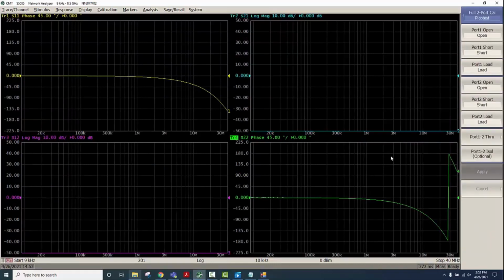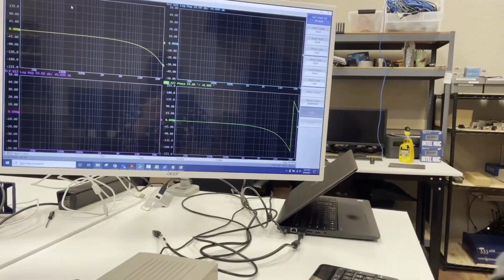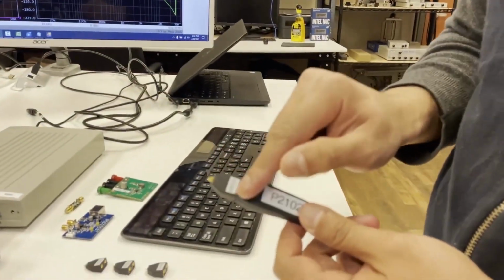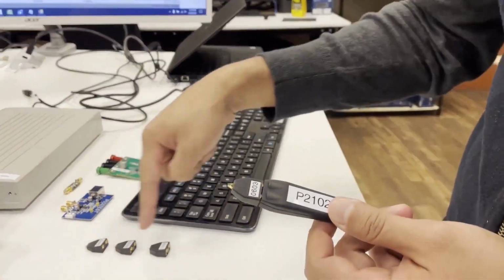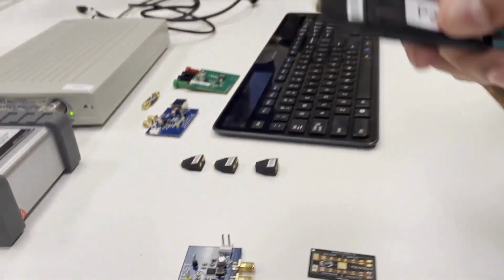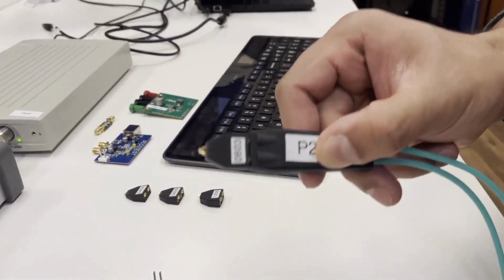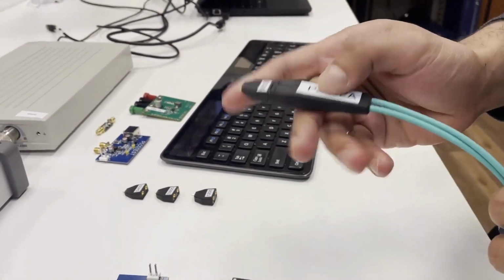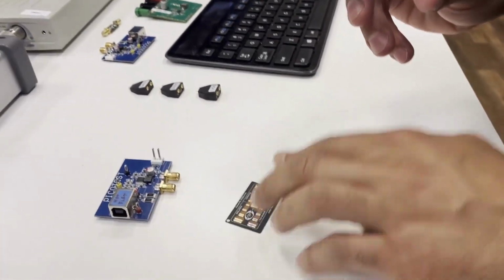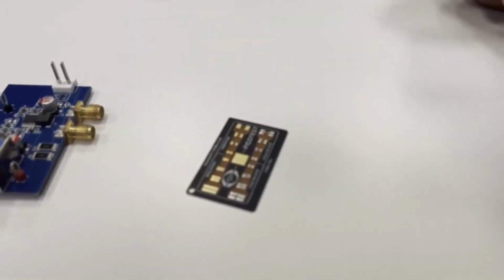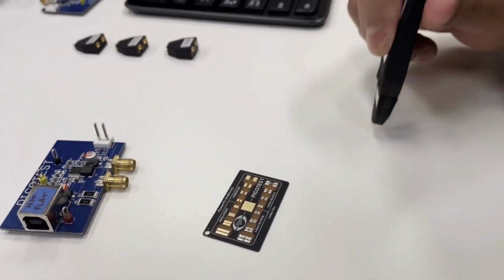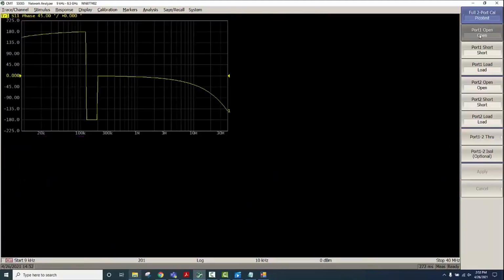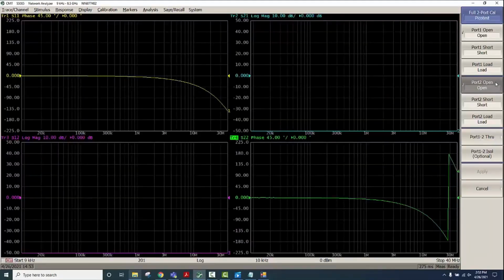We will select the probe along with the tip. So we'll use the 0603, but there are other tips to choose from as well. So we'll be using the same tip to perform measurements, so that's why we're using this for calibration. And now here is the substrate. So first, what we'll do is we'll do an open. So we're not connecting to the cal substrate at this time, so we're just doing the open connection.